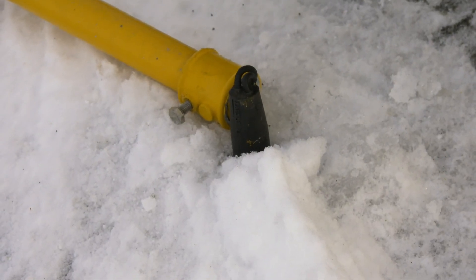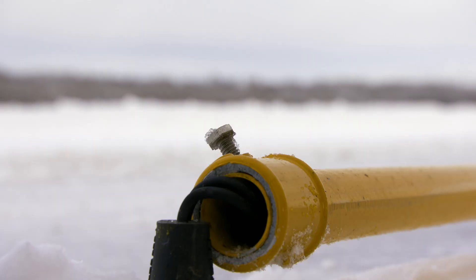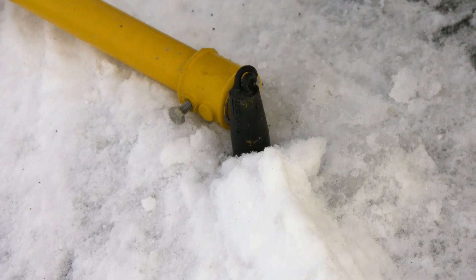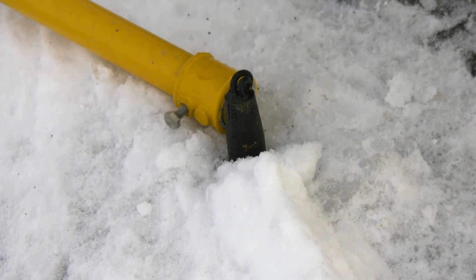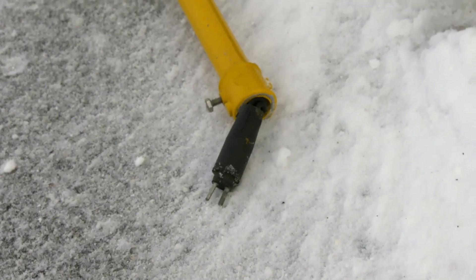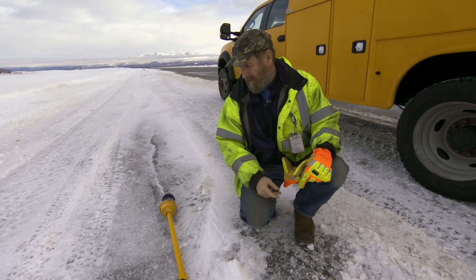This ought to be something we should fix. This is called the coupling, and there's a weak point right on that coupling where it's designed to break away — it's called a frangible. The lights are designed to collapse if they're hit by a plane or snow plow. The frangible breaks easily, leaving the rest of the light intact. Everything looks good on this fixture, so all we need to do is get through the ice, replace the frangible and throw the fixture back in.